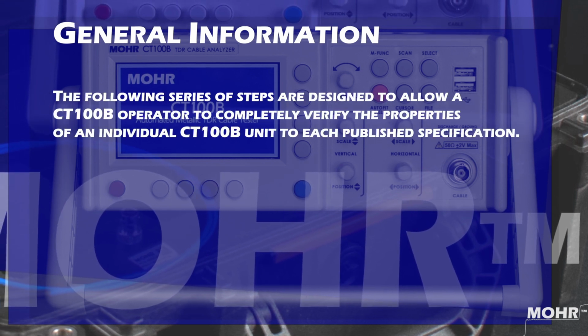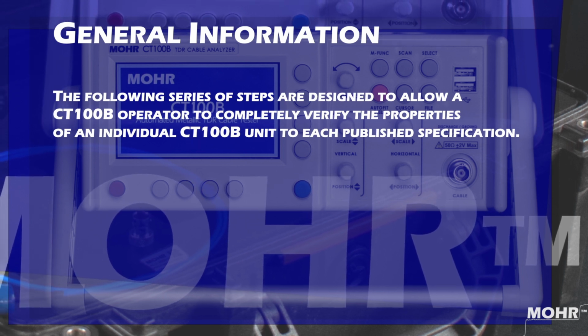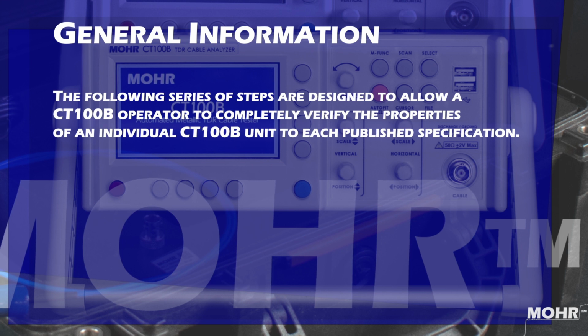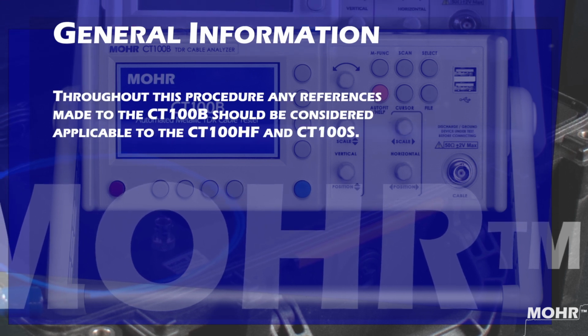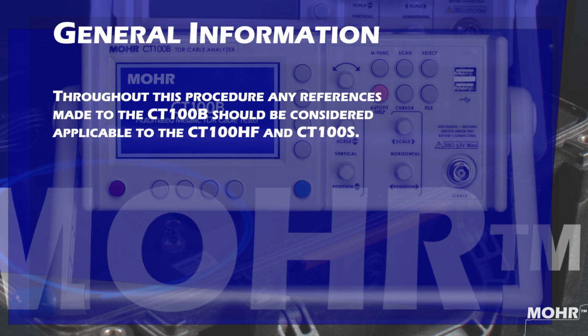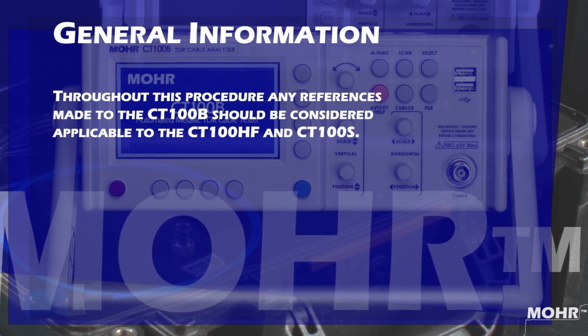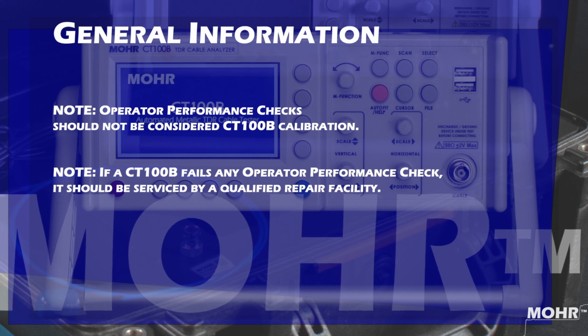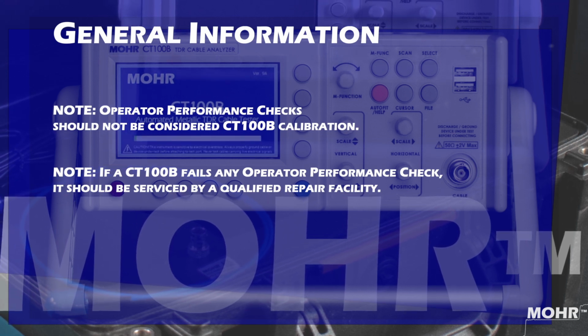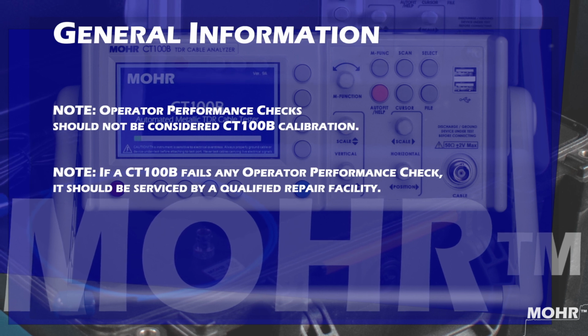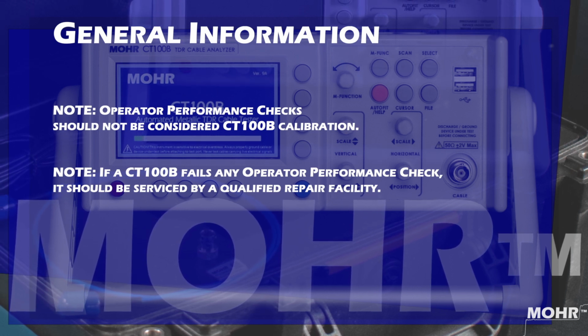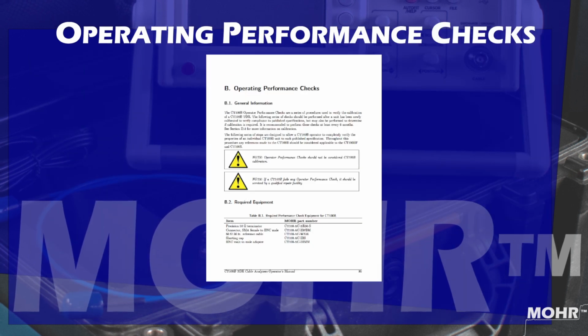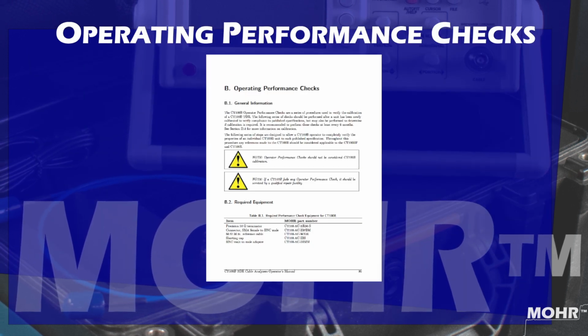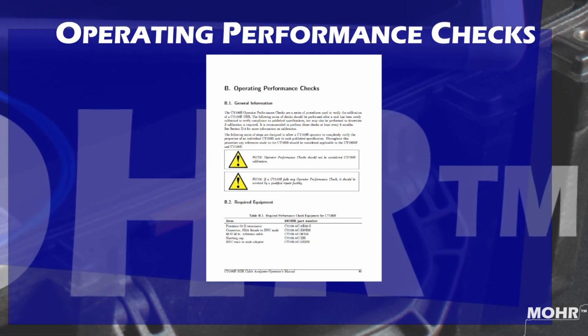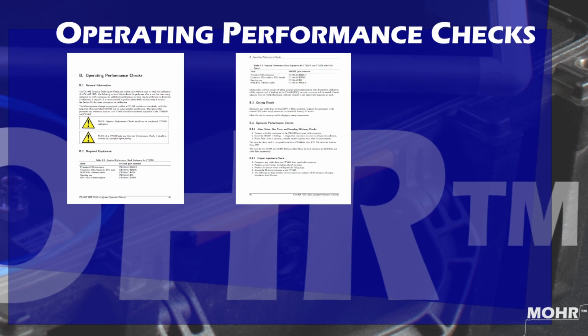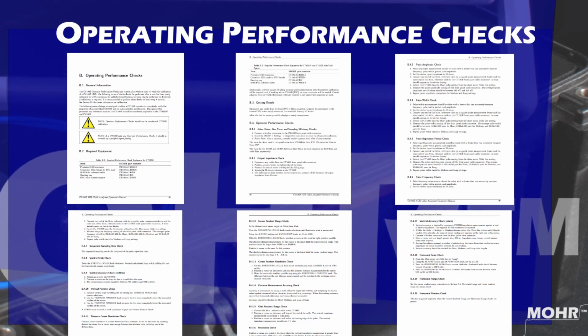These steps are designed to allow a CT100B operator to verify the properties of an individual unit to each published spec. Any references made to the CT100B should be considered applicable to the CT100HF and CT100S. A couple of things to note: operator performance checks should not be considered calibration. If a unit fails any operator performance check, it should be serviced by a qualified repair facility. Operating performance checks are a series of tests compared with specs outlined in Appendix A with the procedures described in Appendix B of the MOHR CT100B Operator's Manual.